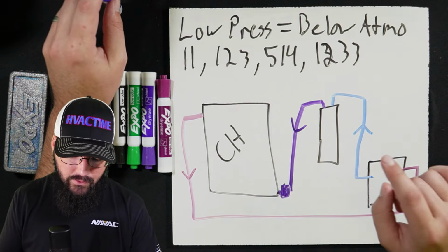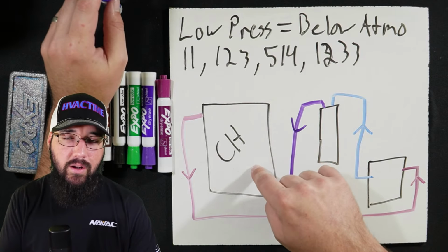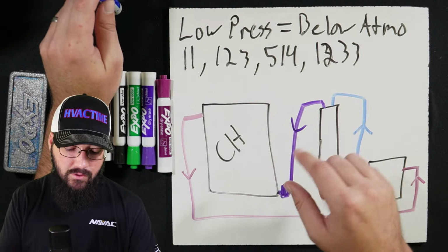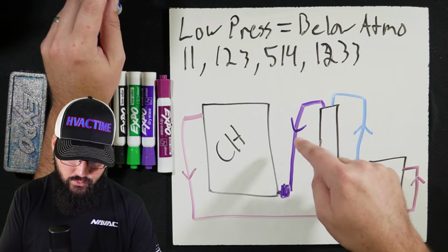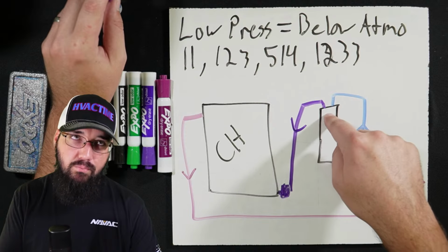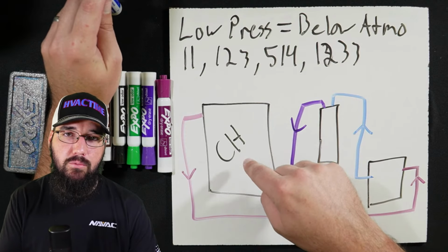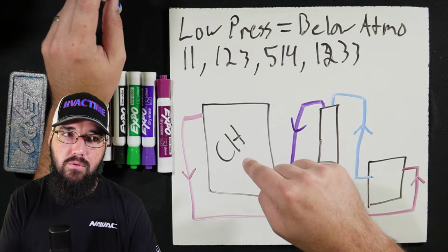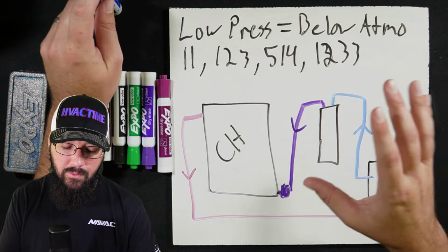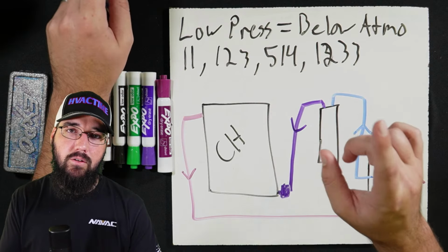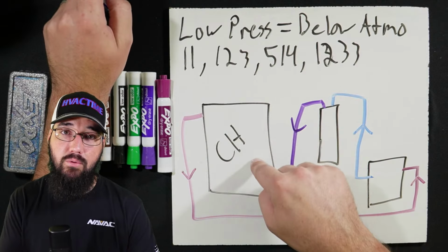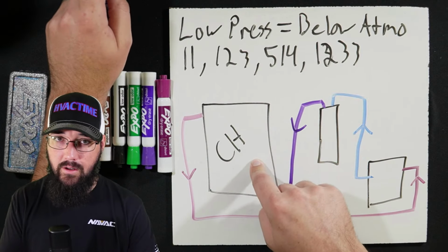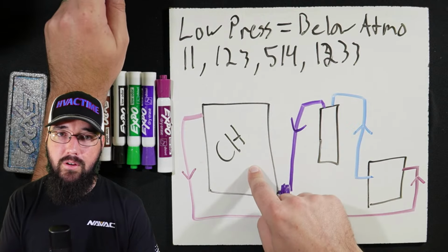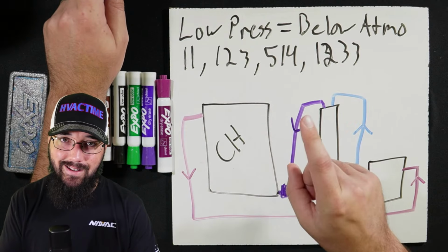Some key notes here. It is recommended, especially if you're wanting to do this by the book, to vapor charge your machine before you start putting the refrigerant in. So some things should be true if you're ready to charge refrigerant. You should have already pressure tested the machine and it held. You should have already pulled an evacuation on the machine and it held.